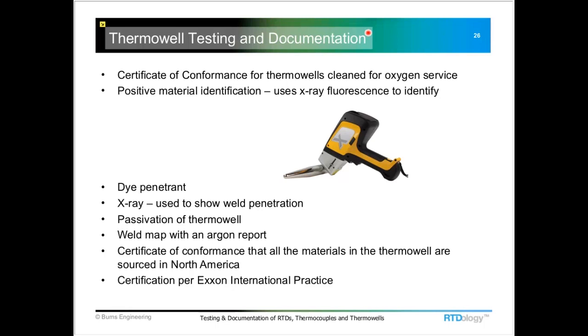So in our poll, I saw where people had selected this positive material identification. So this uses X-ray fluorescence to identify the materials in the well. And so we can actually take a thermowell that's been manufactured. We have the heat numbers. We have the material certification that tells all the components and everything. And so this is kind of the belt and suspenders look at that, so we can actually use this device to verify that, yes, in fact, based on this test, this really is 316L material, for example.